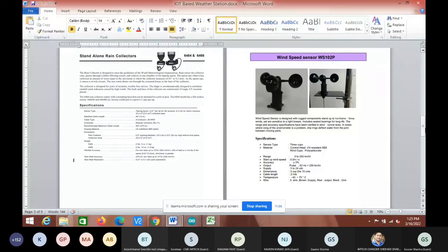Why do we use pre-calibrated data? We aren't using all sensors pre-calibrated, but some sensors in our weather station are. The basic use of pre-calibrated data is you don't have to focus on the calibration part, that's one point, but the accuracy of that sensor also matters. It may happen that if you calibrate an analog temperature sensor, it may not be accurate. So due to accuracy, we choose communication-based sensors, but most of the time we also use analog sensors.